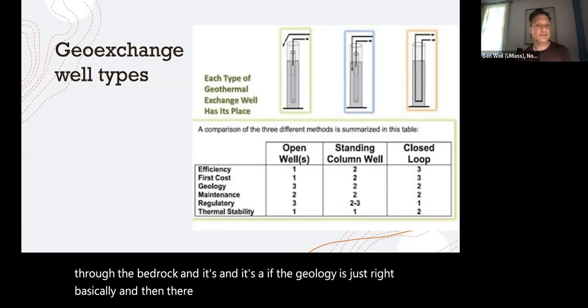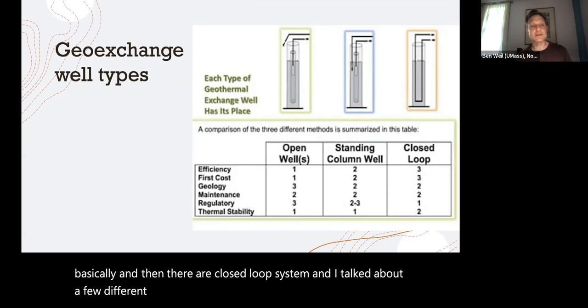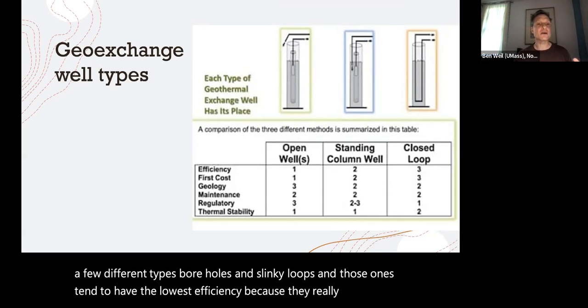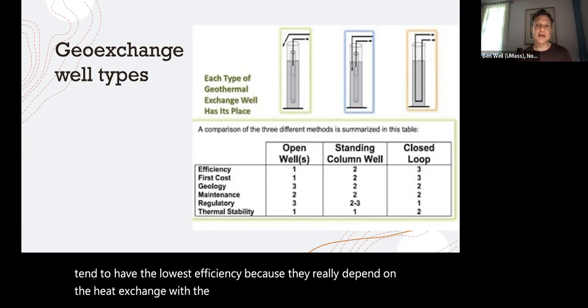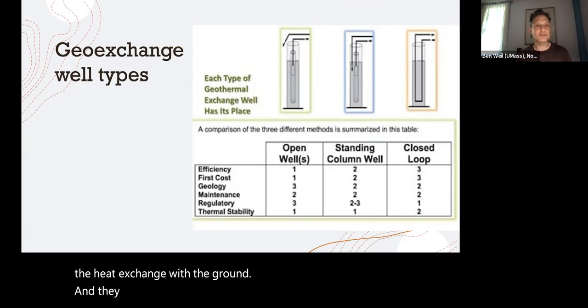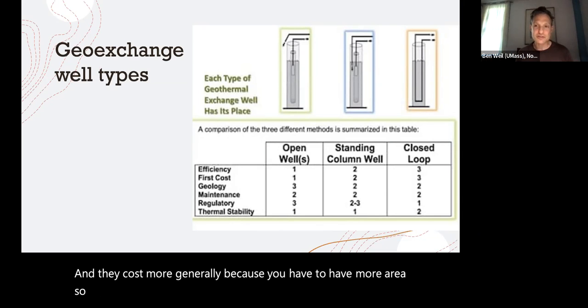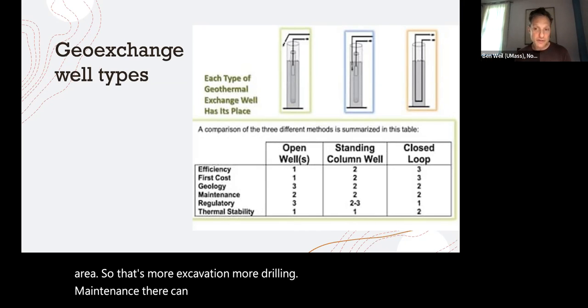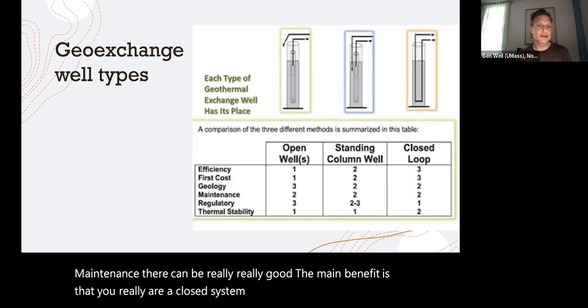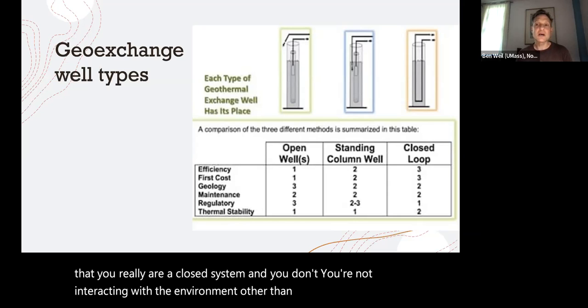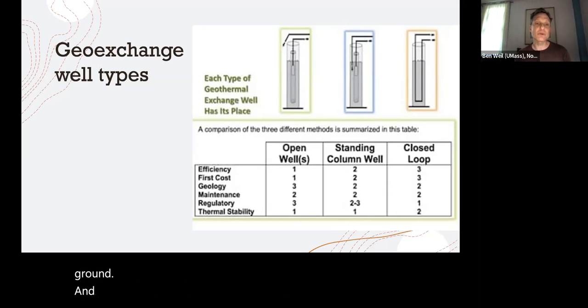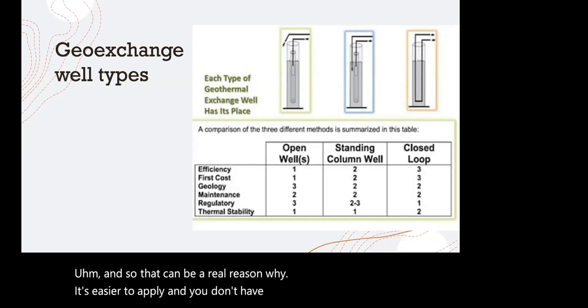And then there are closed loop systems, and I talked about a few different types, boreholes and slinky loops. And those ones tend to have the lowest efficiency because they really depend on the heat exchange with the ground. They cost more generally because you have to have more area. So that's more excavation, more drilling. Maintenance, they can be really, really good. The main benefit is that you really are a closed system, and you're not interacting with the environment other than thermally with the ground. And so that can be a real reason why it's easier to apply and you don't have to jump through as many hoops.